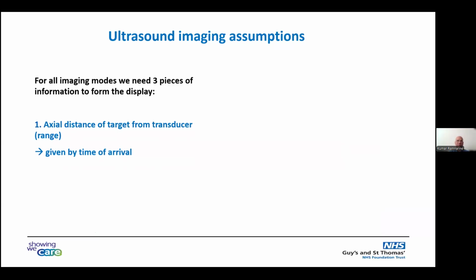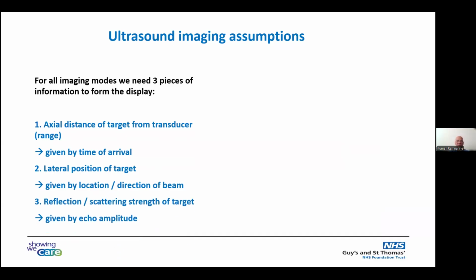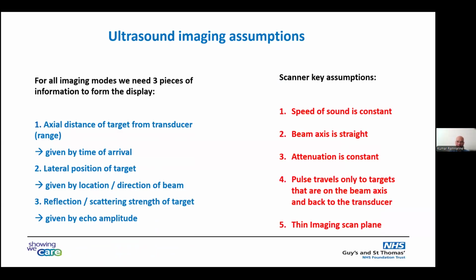In order to create an image, you need 3 pieces of information. You need to know the axial distance of the target from the transducer. This is a range, and this is given by the time of arrival. You need to know the lateral position of the target, and that's given by the location, the direction of the beam. And you also need to know the strength, the reflection of the target, which is given by the echo amplitude. So that's 3 pieces of information that you need in order to produce a grayscale image.